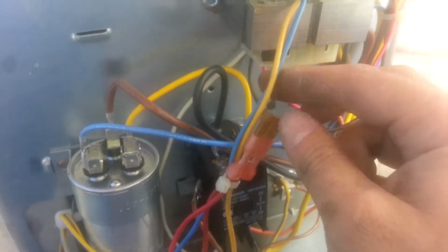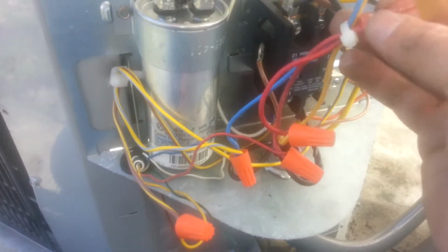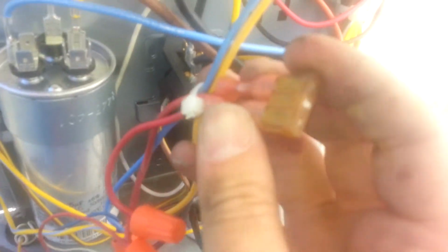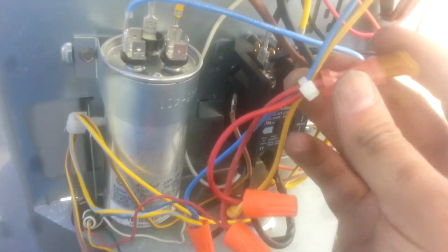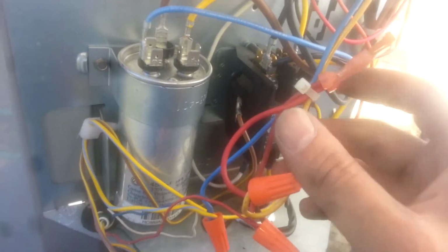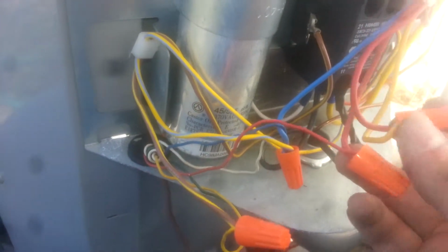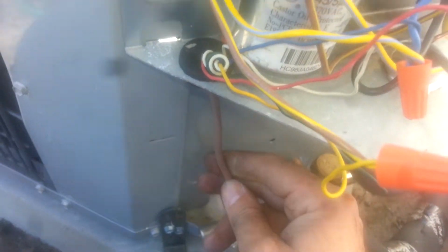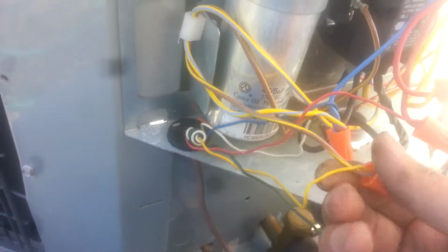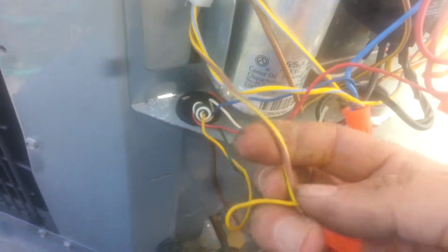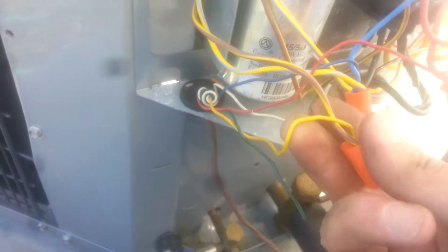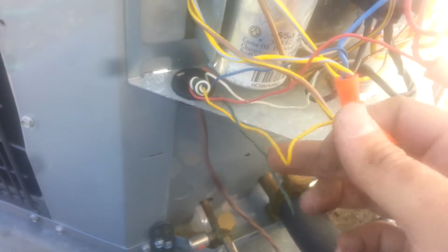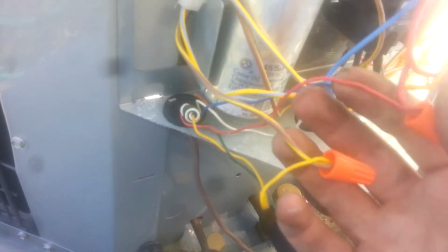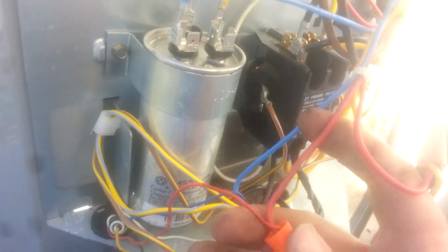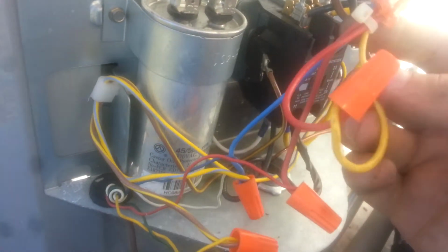I took this low voltage wiring and put in a 5 amp fuse just in case a short happens, so I don't waste a good transformer. So what I did is tie in this low voltage coming in from my house. This is the yellow wire hooked onto the condenser, and this is the yellow wire that goes into the furnace inside the house. This right here is your red, coming in for your transformer.